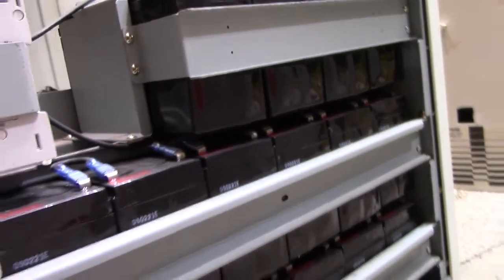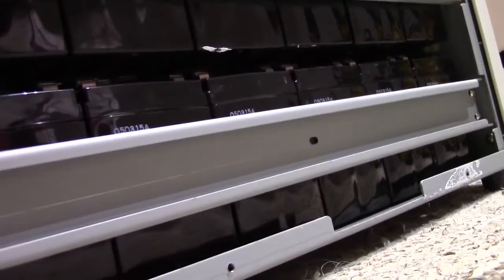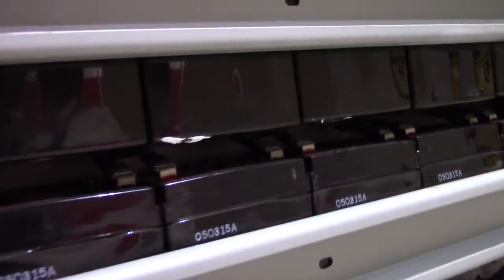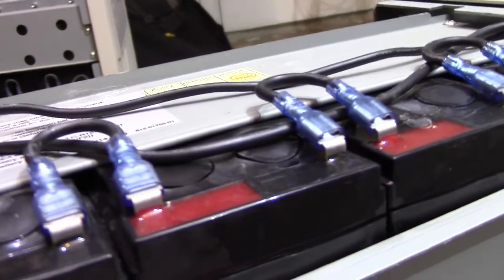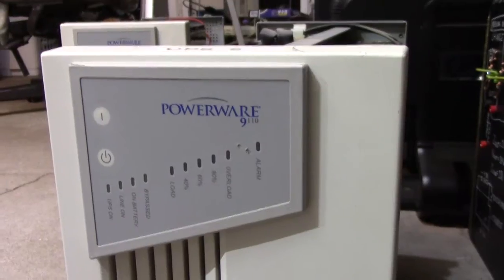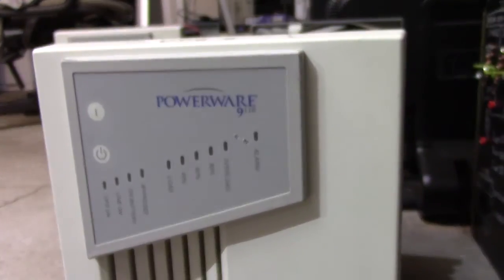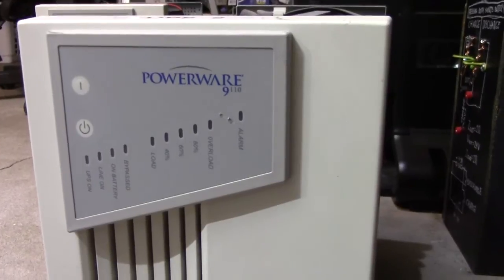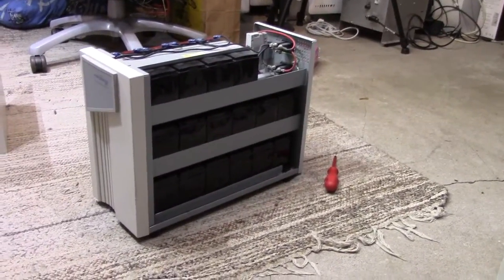For the first time in human history, this beast has been caught and it is resting here, beaten out and destroyed. However, we did not have time to save its last victims — 16 7Ah batteries that truly no longer have a face. So I just brought home this PowerWare 9110 3kVA UPS which came with two external battery packs. And as you saw, it doesn't have any proper battery management whatsoever.